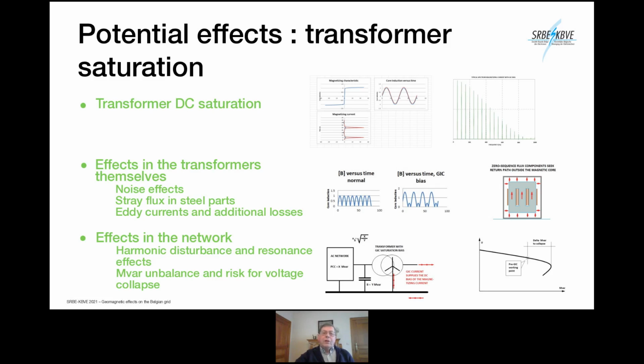And this is the worst effect for the transformer, and has also potential damage, let's say, on the scale of 5 to 20 minutes, 1 hour. You can damage a transformer completely due to heating of the windings, in case of, of course, severe saturation.